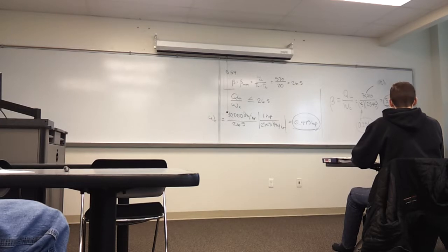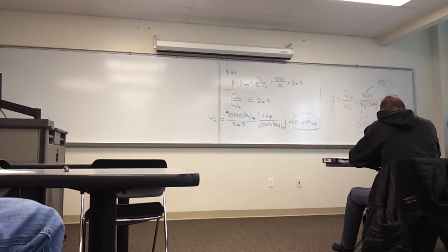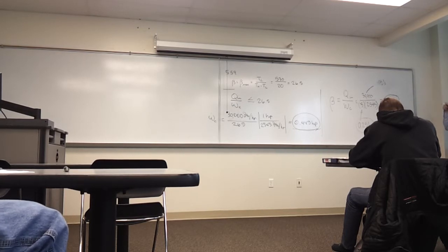That makes sense? Because it says in the problem that we chose a 3-horse compressor. Okay. So if that's the only thing that we're changing, then why can't we buy a half-horse compressor and have it work perfectly fine? Where else is all the losses? Okay, there's always going to be losses, and we'll go through the losses, but in the case of a half-horse compressor, you probably would only be able to pump 1/6 of the refrigerant around the cycle, doing what you want it to do, and that 1/6 would only probably transfer out of the house 6,000 BTU per hour.